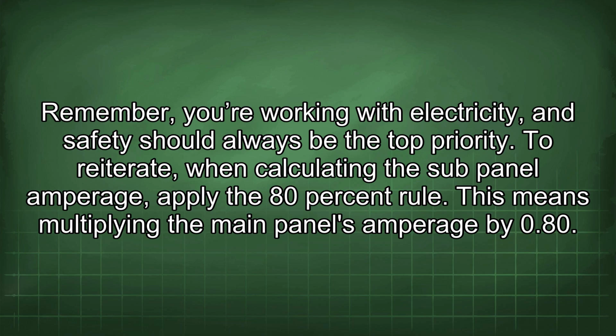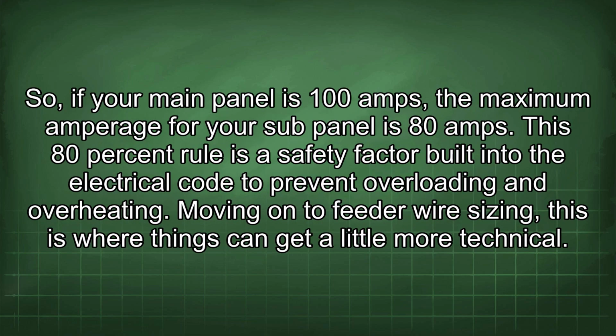To reiterate, when calculating the sub-panel amperage, apply the 80% rule. This means multiplying the main panel's amperage by 0.80. So, if your main panel is 100 amps, the maximum amperage for your sub-panel is 80 amps. This 80% rule is a safety factor built into the electrical code to prevent overloading and overheating.